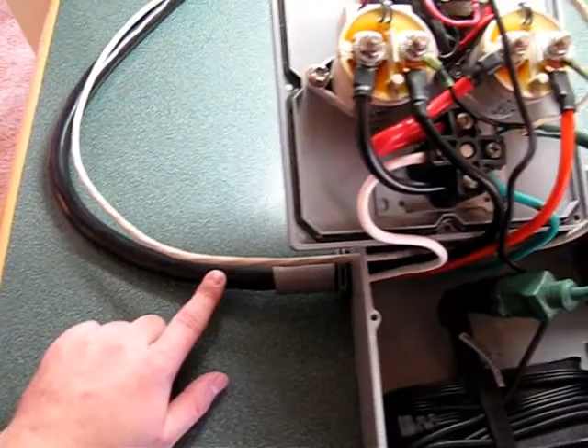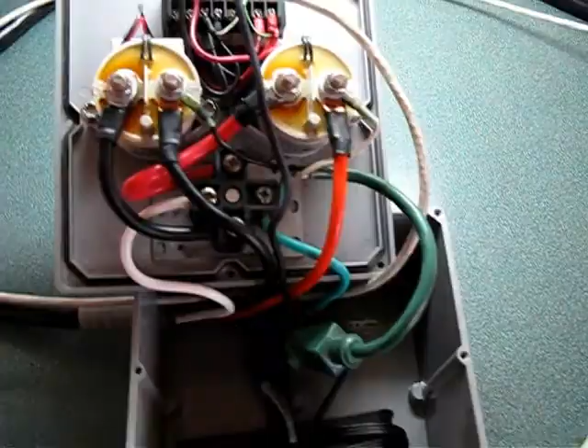Basically, before, we had a cable coming in from the car that would be hardwired to the charge port on the side of the car, going into the white here for the neutral, the black here for one of the hots, the red on this side for the other hot, and then the green coming in for the ground. So that connected neutral, hot, hot, and ground, with the hot being separated by these contactors going into this particular connector.